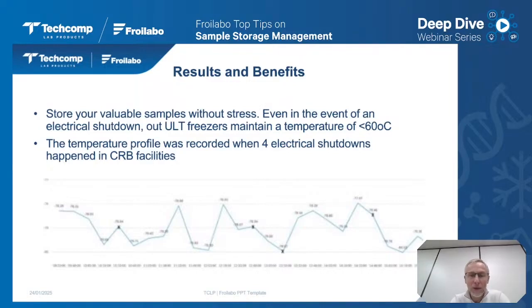As you can understand, it was not expected, but they measured the temperature profile in these conditions. You can see on the slide that even with 4 electrical shutdowns over several hours, marked on the graph with an arrow on the temperature profile, the temperature stayed between minus 80 and minus 78 degrees. That means we can guarantee very safe sample storage with our units, including the latest improvements.